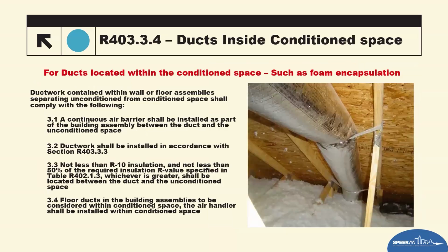Speaking of foam and how it's being addressed in the code now, this actually explains any ducts that are listed as part of or inside the conditioned space. There are things now that are required to take place in walls, floors, and ceilings. With me doing inspections, a lot of times I saw ducts like you see in this picture crammed against the roof deck. I know we see fluffy stuff at the bottom, but if you could picture this being foamed, they're just going to spray foam around it. That's no longer allowed. You actually have to have at least an R10 between the roof deck and the duct if it's part of or inside the conditioned space.